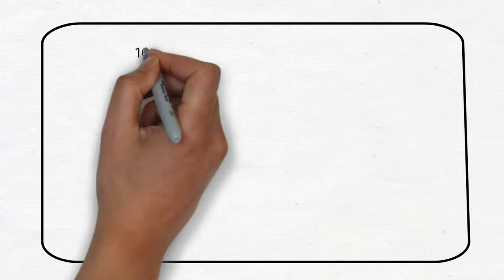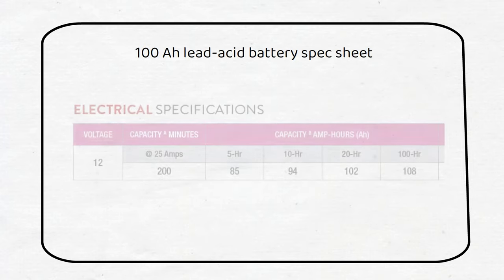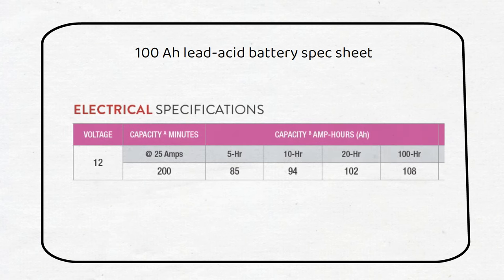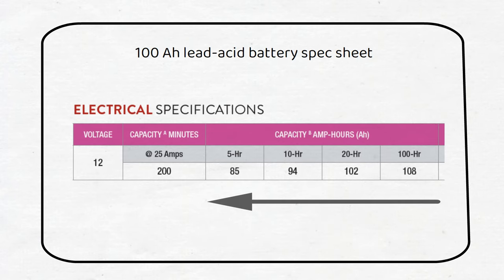If we go higher than the rated C-Rate for lead acid, we will reduce the battery capacity. Let's take a look at this graph from a popular lead acid battery. We can see that the battery capacity in amp hours is reduced when the C-Rate rises. This is because there is more heat generation and more internal resistance. The battery will become less efficient. This is important in sizing your system.